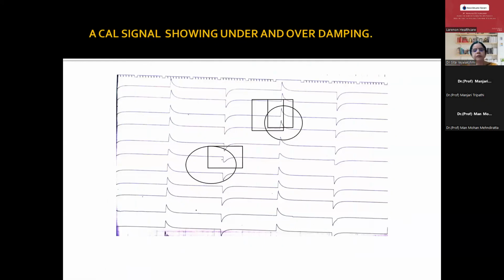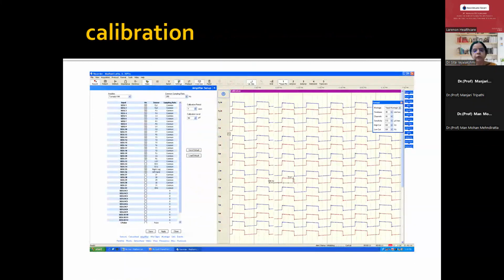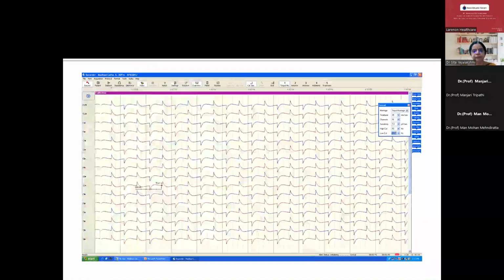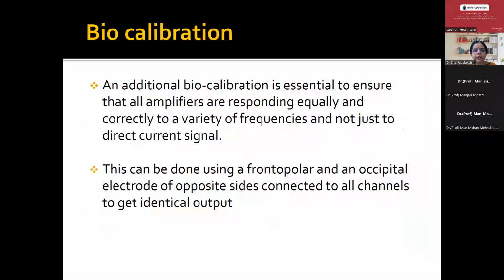But with digital machines, life is very smooth, because there is no pen touching the paper. Most of the time when we check the calibration, it is very nicely aligned, and this is the mechanical calibration we see in a digital machine. Again, you see this when you give a 50 hertz current. This is what you receive during the mechanical calibration.